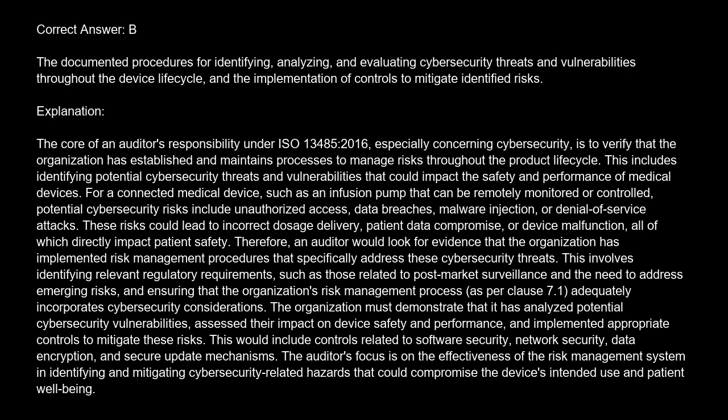For a connected medical device, such as an infusion pump that can be remotely monitored or controlled, potential cybersecurity risks include unauthorized access, data breaches, malware injection, or denial of service attacks. These risks could lead to incorrect dosage delivery, patient data compromise, or device malfunction, all of which directly impact patient safety.